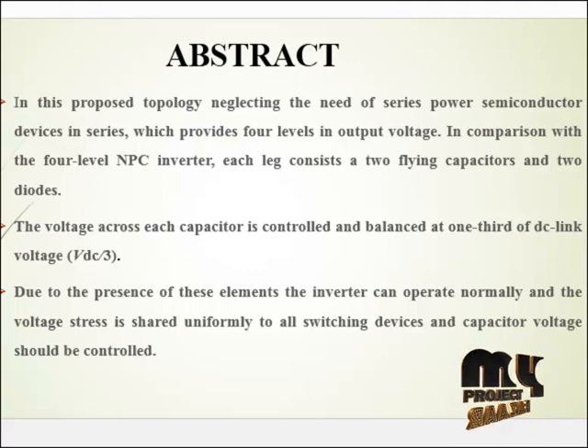In this proposed topology, neglecting the need of series power semiconductor devices provides 4-level output voltage in comparison with the 4-level NPC inverter. Each leg consists of two flying capacitors and two diodes. The voltage across each capacitor is controlled and balanced at one third of DC link voltage. Due to the presence of these elements, the inverter can operate normally and the voltage stress is shared uniformly to all switching devices, and capacitor voltage should be controlled.